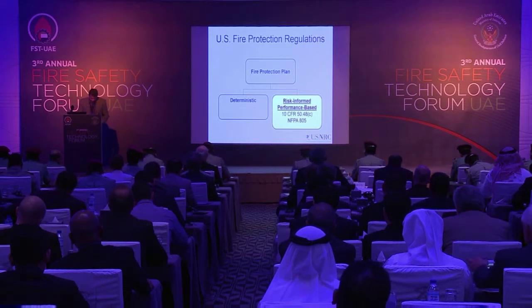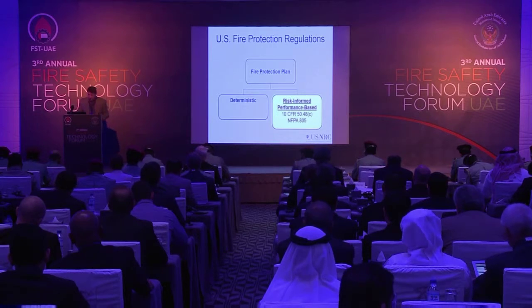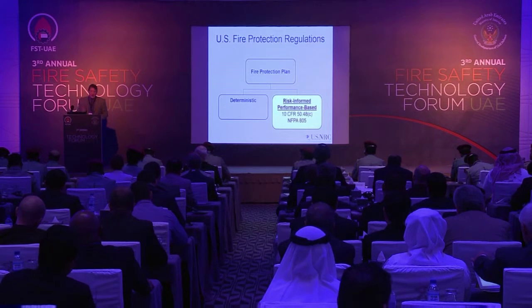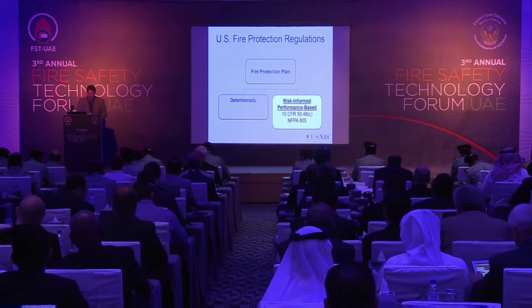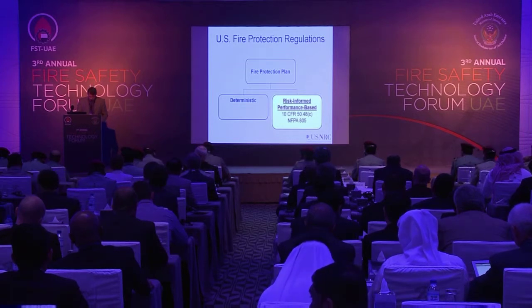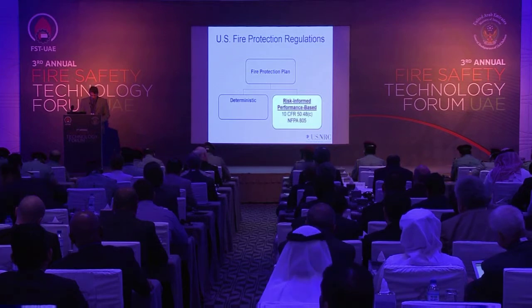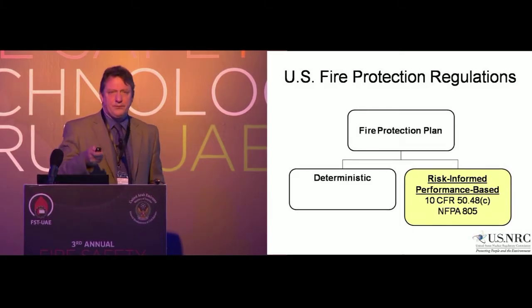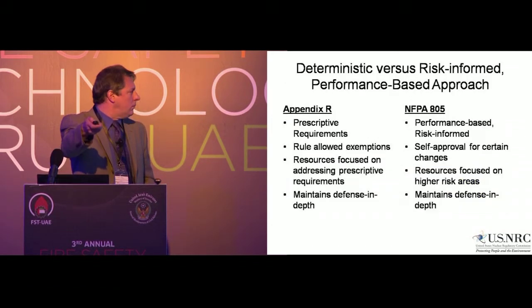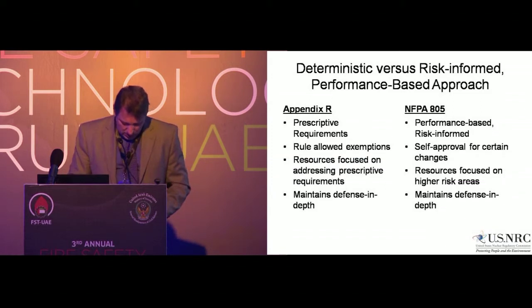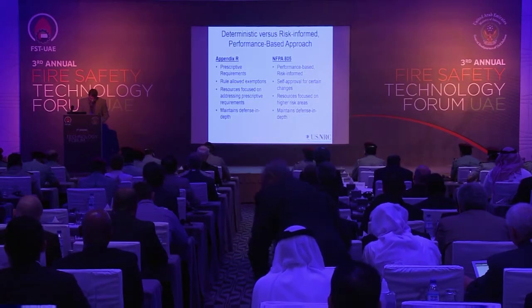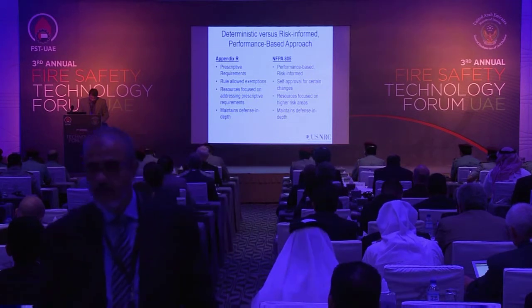And part of that is doing site audits where we go out and do walk downs of the plant and discuss the plant modifications, look at fire modeling, look at their fire PRA or PSA. So it's a very resource intensive process, but well worth the results. NFPA 805 enables leveraging the state-of-the-art in fire protection evaluation techniques to maintain and enhance safety. It establishes fundamental fire protection program and design requirements for fire protection systems and features, and it allows nuclear safety performance criteria to be satisfied by using both fire modeling and fire risk evaluation.